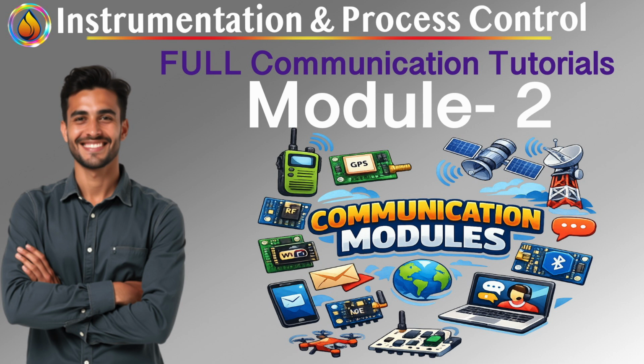Module 2, Physical Layer Mastery, RS232 and RS485, where noise kills data. Now we stop talking philosophy and start talking physics. Up till now, everything we discussed could live happily on a whiteboard. From here onward, electrons, ground potentials, motors, VFDs, and bad earthing enter the room. And once they do, noise becomes the real boss. This module is about understanding why some links survive plant floors and others die quietly at commissioning.